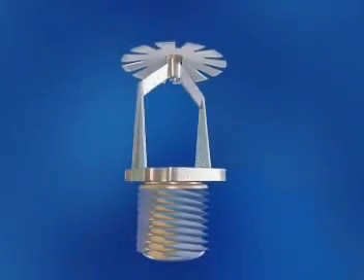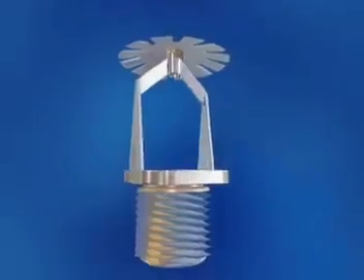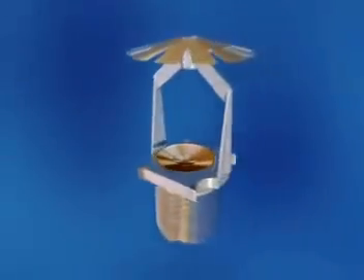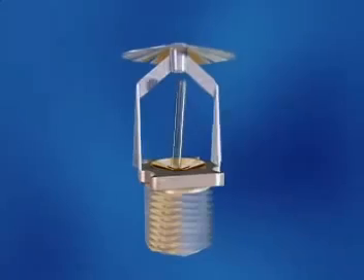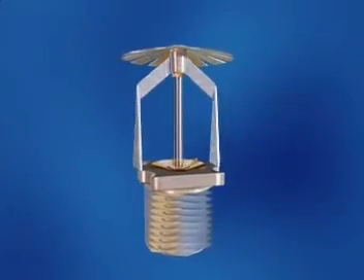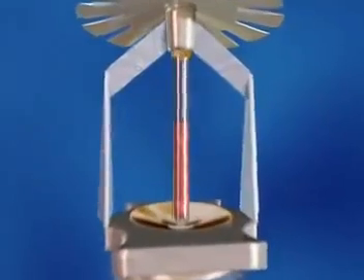A typical sprinkler head comprises a threaded body to connect to pipe work with a valve seal to hold back the water. The valve seal is retained by a glass bulb which contains a liquid that has a high coefficient of expansion.